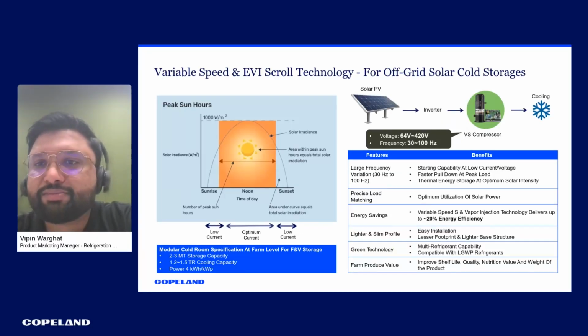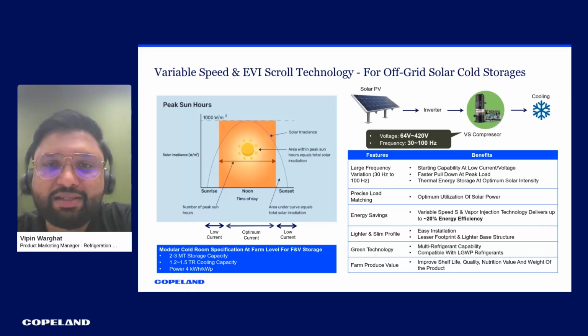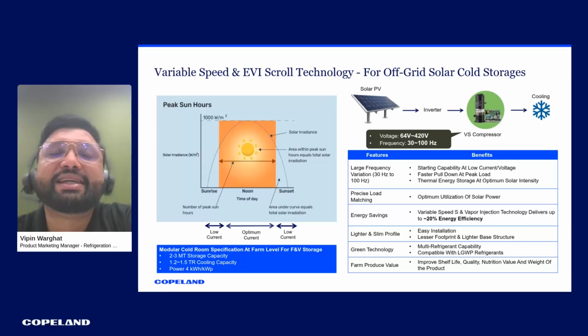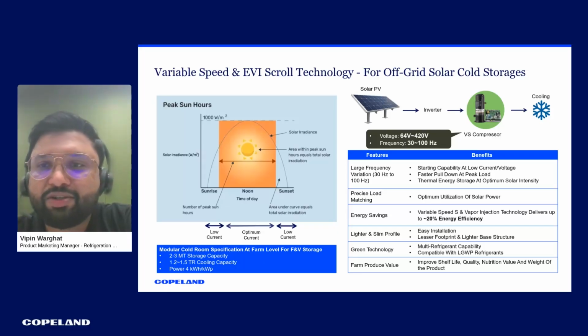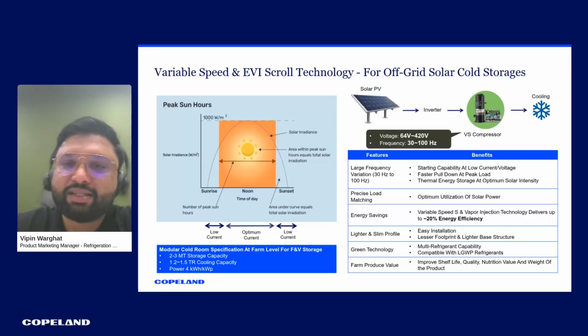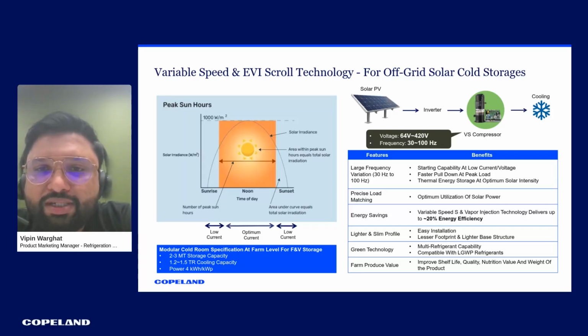So basically, this is for an off-grid solar cold storage. The challenges here are the differences in power intensity because of the irradiation of solar radiation during the day, and since this is an off-grid solar cold storage, it was also required to work during the night time when solar radiation is not available. So the variable speed compressor offered by Copeland was not only able to mitigate these challenges by handling the voltage and frequency fluctuations, but it also delivered the required demand.